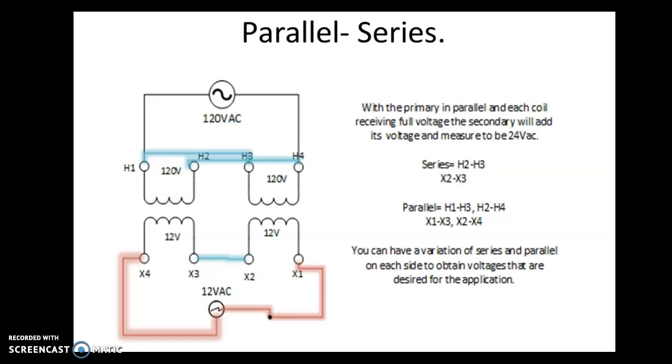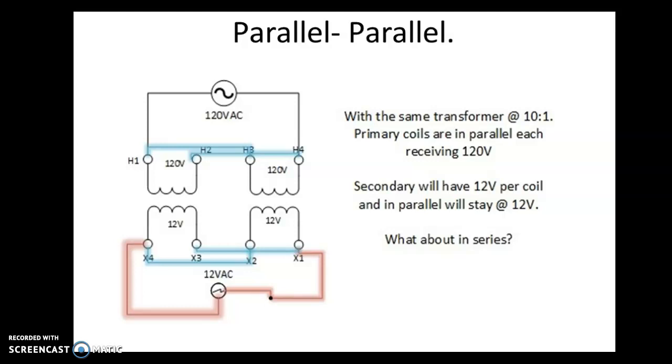Some of the things to denote for this is that a series connection is typically H2 to H3, X2 to X3. Parallel connection is 1 to 3, 2 to 4, 1 to 3, 2 to 4. We can see that again here.